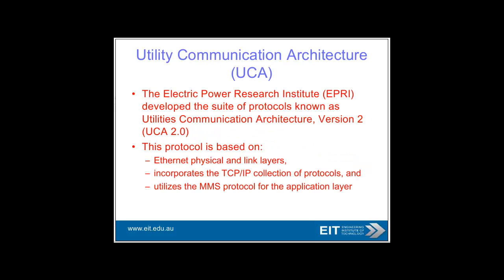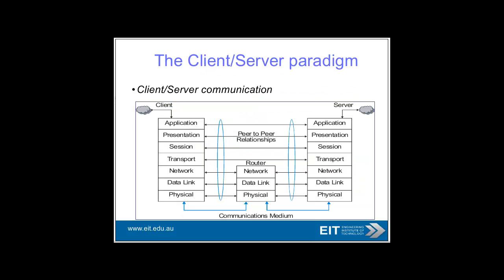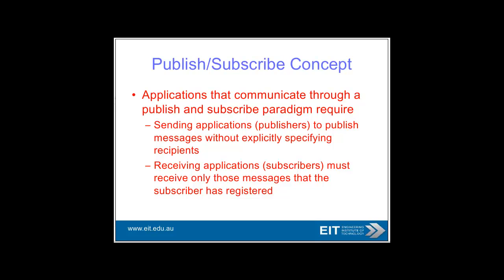The EPRI — Electric Power Research Institute — developed a suite of protocols known as UCA, which is based on Ethernet and incorporates TCP/IP and uses MMS protocol. The first version came out in 1991, and that is obviously the precursor to the substation solution. It's all based around the client-server paradigm, where the client is where you extract information from the server. Another important concept is the publisher-subscribe approach, often used with protocols such as DeviceNet from CAN bus, which is an automobile industry protocol.